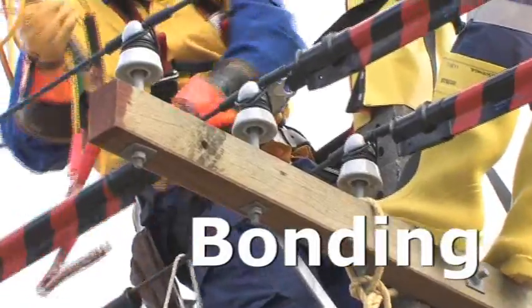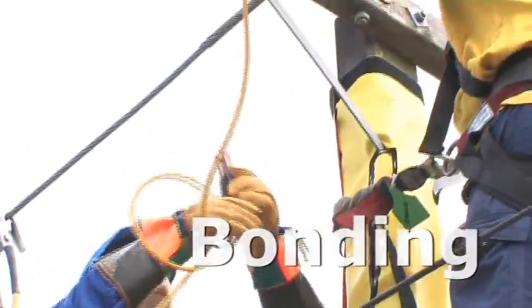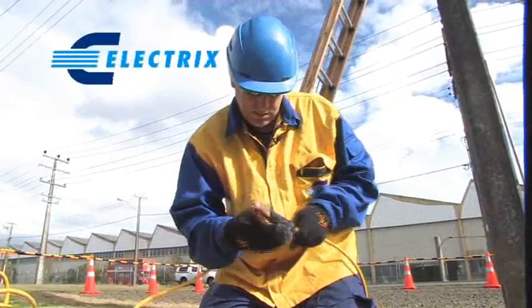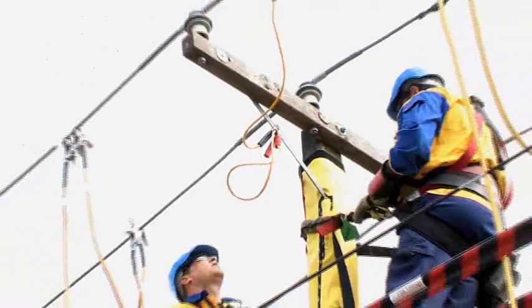All exposed metal work should be bonded to a common point. The EEA guide recommends a copper lead of at least 25 mm square. Electrix has developed a practical lead consisting of three battery jumper clamps and a copper braided cable of the required size. Due to its unique design, one lead can bond several items.